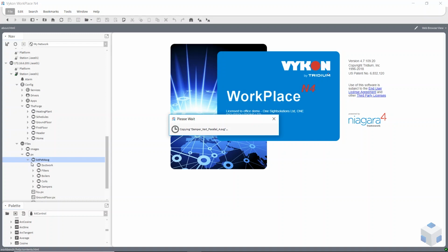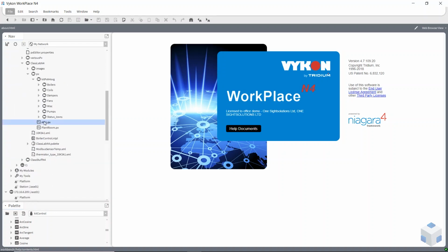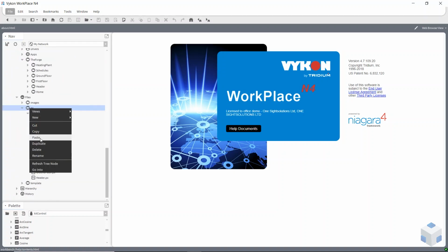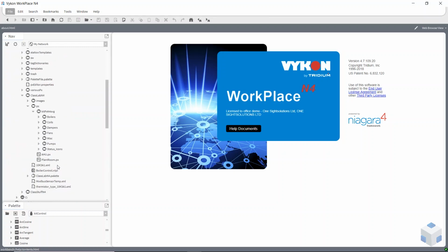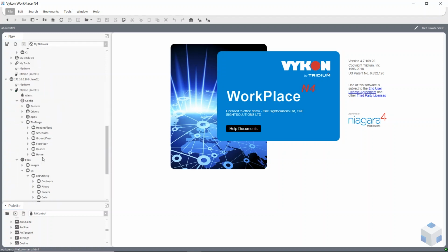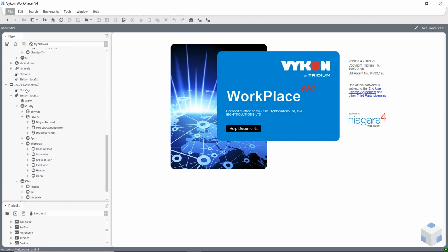The next thing is to add some px pages that have been partially completed. So again, here they are, AHU and plant room. Copy those, right click on them, copy them, and paste those onto px. Okay, so now we've got some partially completed stuff, and I'm just going to be doing the AHU one, which is our BACnet points. So if I go to our BACnet on our station on a remote host, and this is my device, this is where I'm going to have to create a new view.